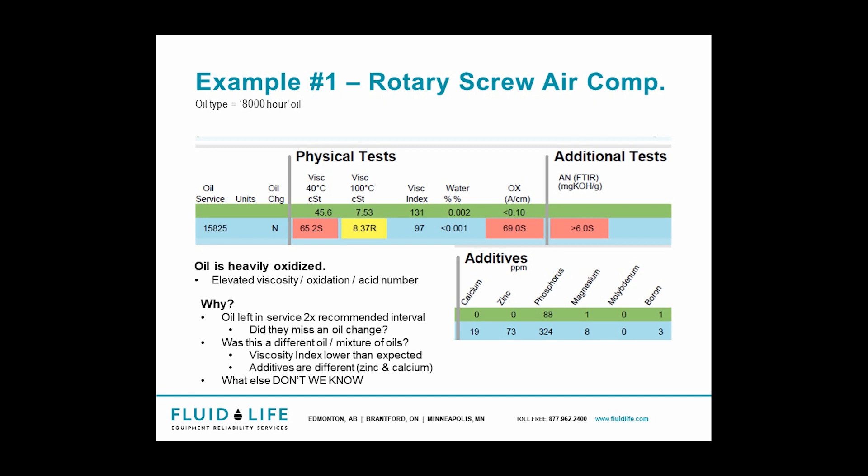It could be that an oil change was missed and we have 16,000 hours. But why was the oil change missed? Could it be the equipment couldn't be shut down at production? Perhaps it was missed on the schedule, or simply perhaps there were weather issues. Solutions include maintaining regular maintenance intervals and making sure that everything is tracked to ensure nothing is missed when it comes to oil changes.